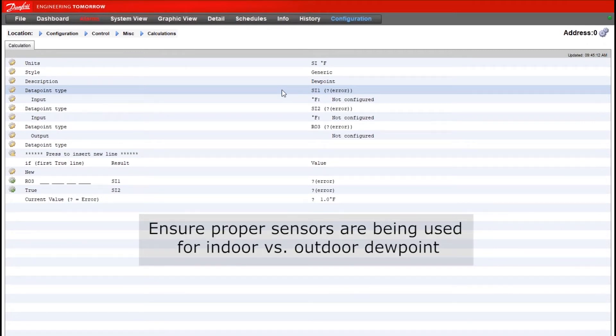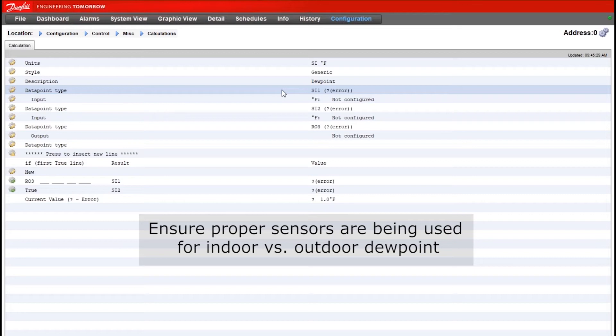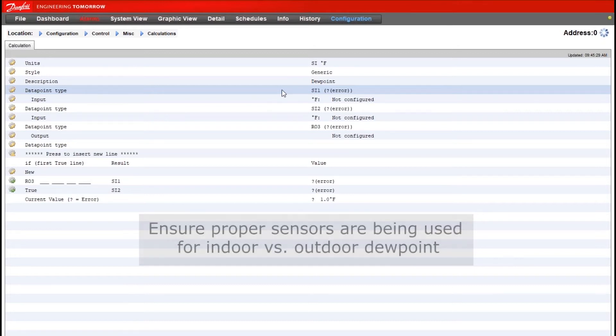So are we calculating indoor or outdoor dew point? If it's indoor, then we need to know what our indoor RH or relative humidity and then our indoor temp sensor values are, making sure they're assigned in the program. And then the same if we're calculating outdoor dew point in this calculation. We need to know what the outdoor temperature and the outdoor humidity values are so we can bring them in.